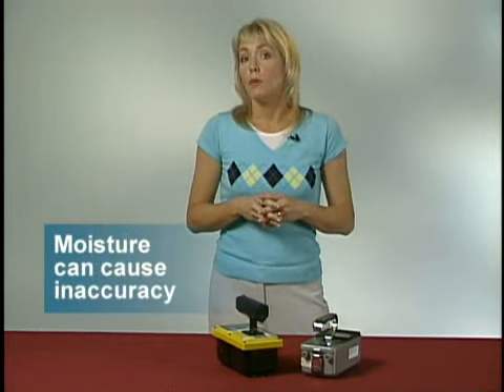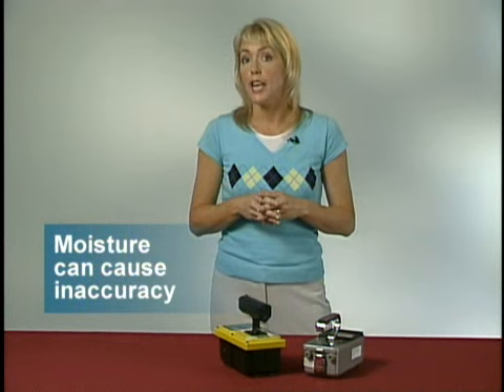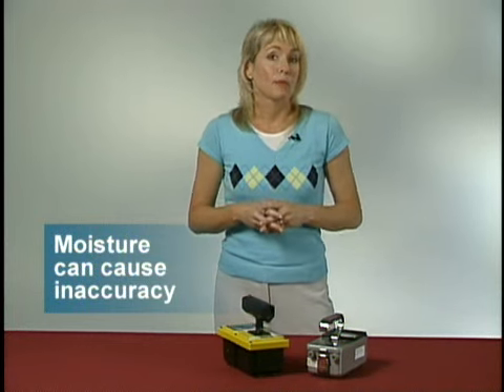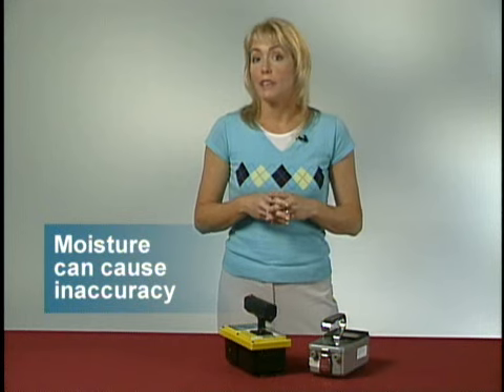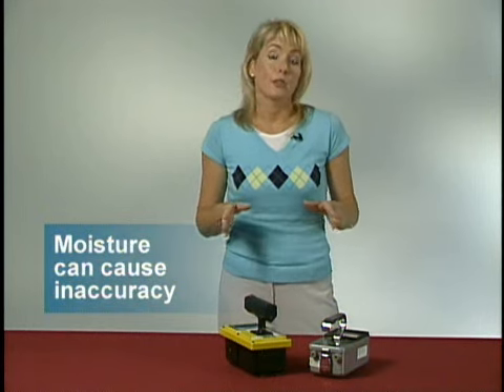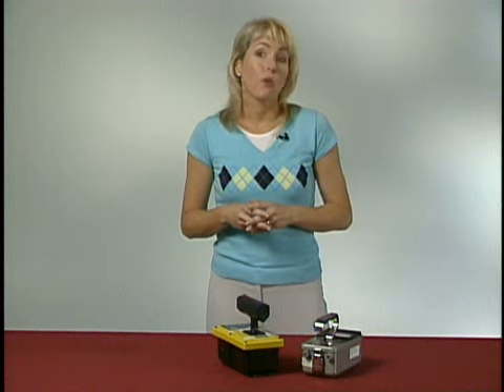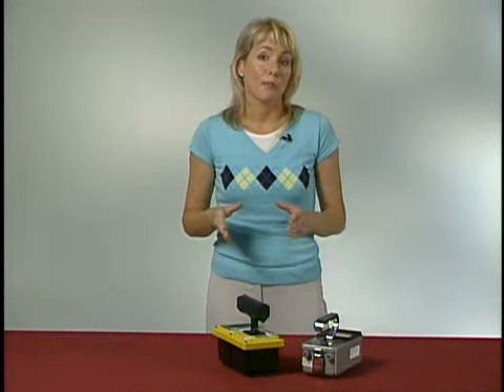Finally, an ion chamber will read too high if moisture gets into the chamber. This is a common problem because most ion chambers are open to the atmosphere, and the atmosphere contains water vapor. To prevent this from happening, ion chambers are designed so that the air must go through a drying agent, typically silica gel, before it gets into the chamber. One thing you can do to help keep your ion chamber in operating condition is to store it in a sealed box or even a plastic bag that contains silica gel.